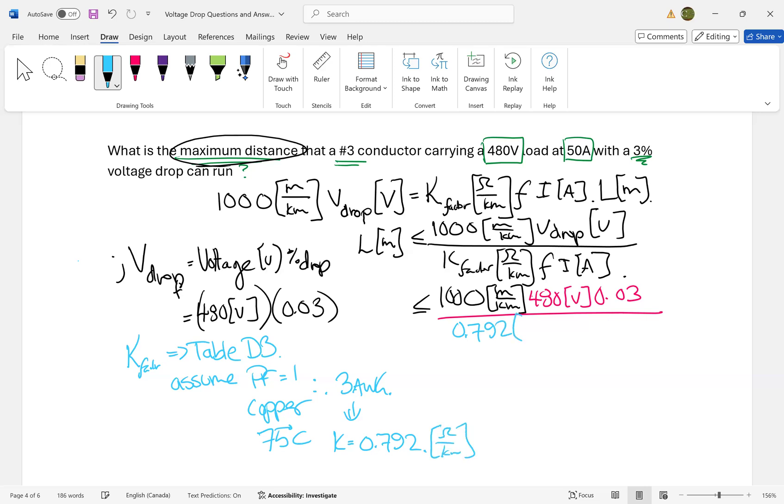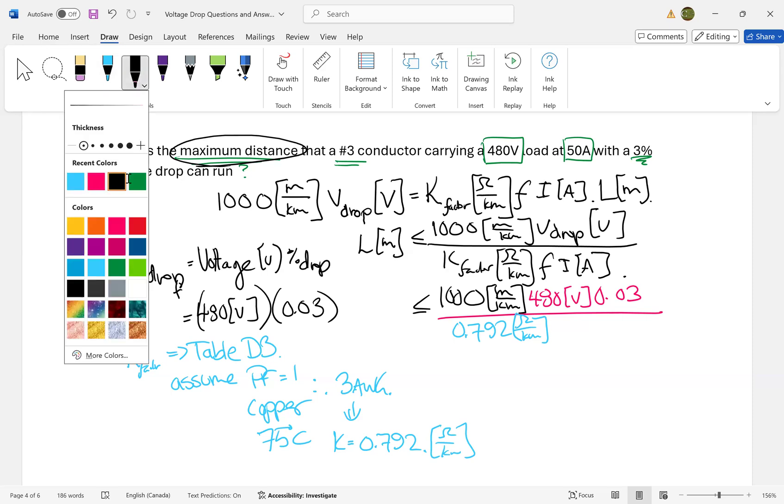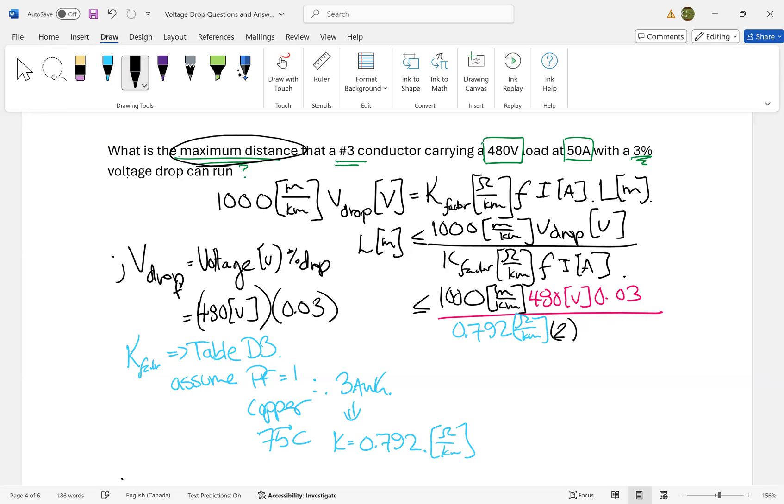Do not do calculations without units - units help you see if you're right or wrong. F = 2 from Table D3 Note 2, and we're operating at 50 amps. Calculating: 14,400 divided by 79.2. Checking units: meters and volts on numerator, kilometers and ohms per kilometer on denominator, times amps. Volts and amps equal ohms, kilometers cancel, leaving meters.